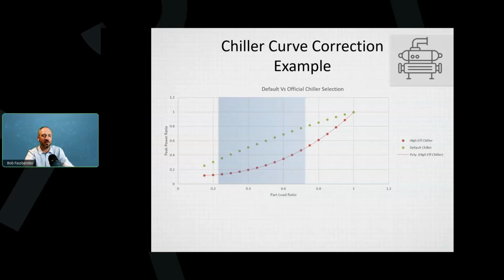And if you're a performance contractor and you predict that and then the building outperforms what you expected, that's great. But if you're trying to get money for your model and show that it shows savings, that's terrible. So the bottom line here is curve 1 in green and curve 2 in red. The red curve improved the chiller energy by 50%, a net 8% on the project. And that's something that people don't even see. And pretty much every piece of equipment has that going on in the background.